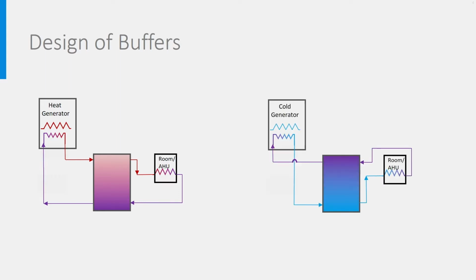A cold buffer would be designed similarly, but this time the tank is tapped at the bottom, where the water is the coldest. When the tank is cold, it can deliver cold to the rooms and the air handling unit, while the generator is off, avoiding in this way too many short on-off cycles. It is very important that the tank is stratified, making sure that there is hot water above and that it does not mix too quickly with the cold water below. The tank must be well insulated to avoid heat losses that would decrease the overall efficiency of the system.